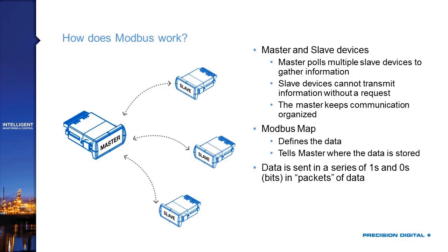When master and slave devices communicate, they use one of those buses we discussed earlier — sending series of zeros and ones in data packets. The Modbus protocol defines what that data packet looks like: so many bits for the device address, so many bits for the register, so many bits for a function code (like 'write this data' or 'send back this information'), then bits for the data, ending with error checking. That format is really what Modbus is all about.